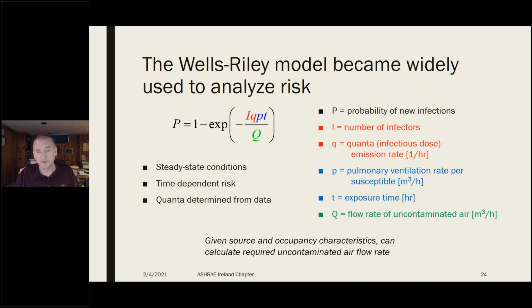So how do we determine what these targets should be? The Wells-Riley equation, the Wells-Riley model, has been used extensively as a basis for analyzing infection risk during the pandemic, and it still remains probably our best tool. It has its limitations, but with it we can set a target for infection risk. By defining a scenario with an assumed number of infectors, their output of infectious quanta, how long they're in an environment with susceptibles, and the pulmonary respiration rate of those susceptibles, which determines their dose, we can determine the clean air flow rate required to achieve that target.